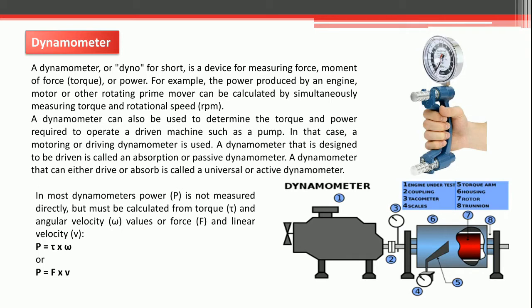Now in the case of this dynamometer, an absorbing dynamometer acts as a load which is driven by the prime mover under test, and the dynamometer must be able to operate at any speed and load to any level of torque that the test requires. The dynamometer has a braking torque regulator where the power absorption unit is configured to provide a set braking torque load, while the prime mover is configured to operate at whatever throttle opening, fuel delivery rate or any other variable is desired to test.